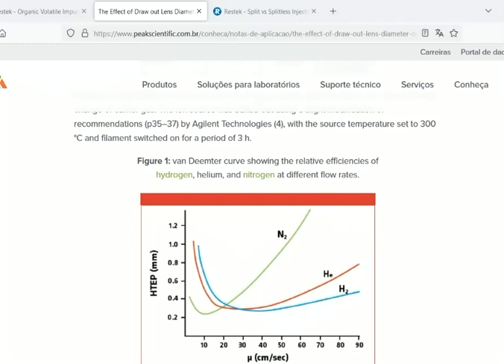After determining whether you're going to use a split or splitless, one of the next things will be what your flow is going to be. Here you can see where a lot of the flows come from — this is height equivalent to theoretical plates, and here's the rate of gas transfer through the column. What we want is fast transfer through the column and the most theoretical plates, or the least height equivalent theoretical plates. You can see helium is better, hydrogen is the best, but hydrogen is dangerous. So around 30 to 35 is usually where you'll see a lot of flow rates set in a method, and maybe up to 40 or so.